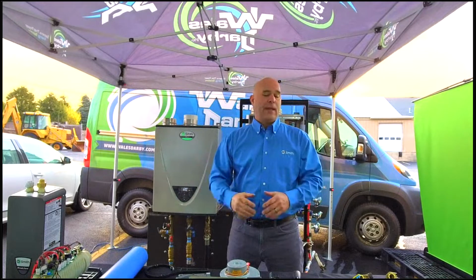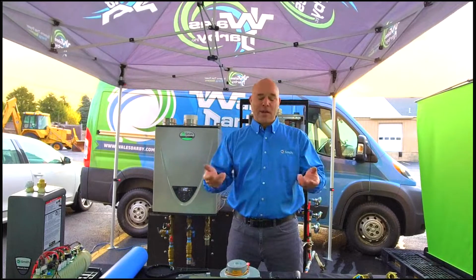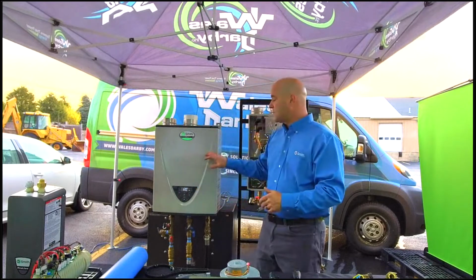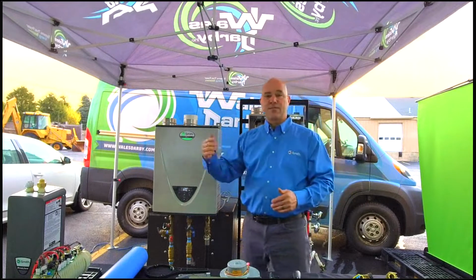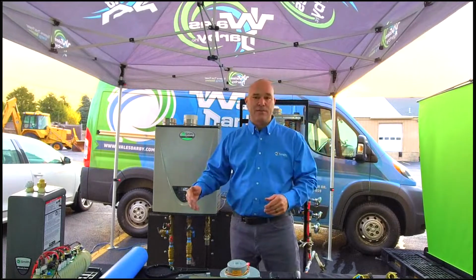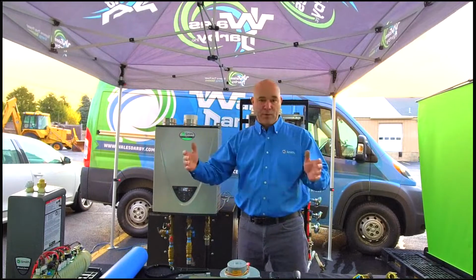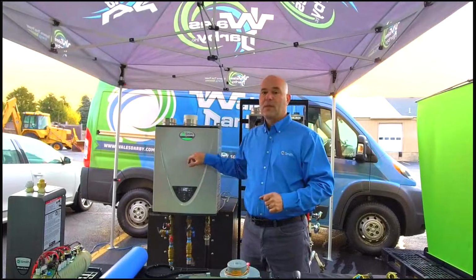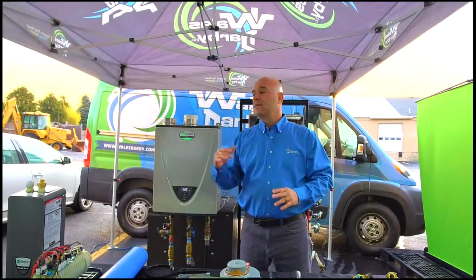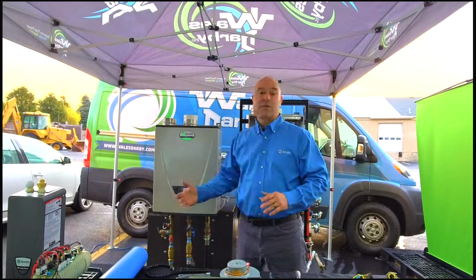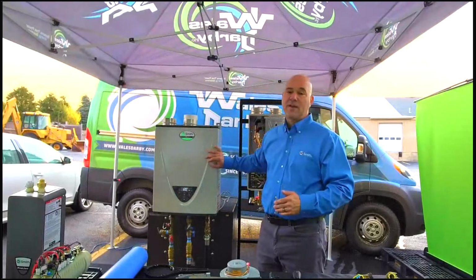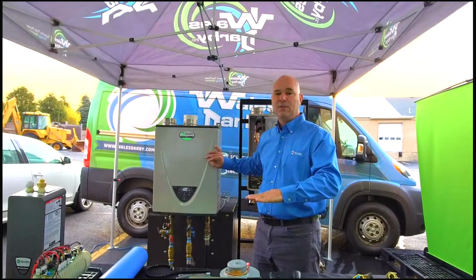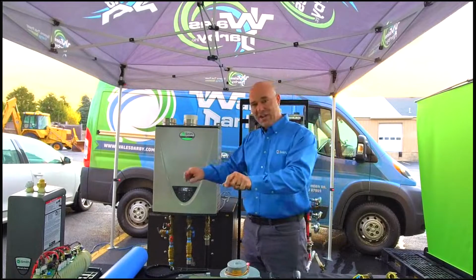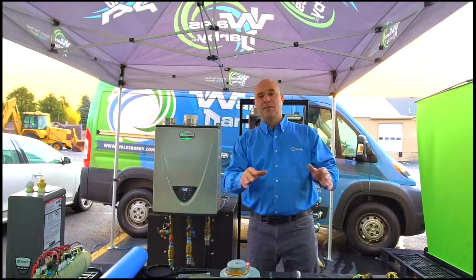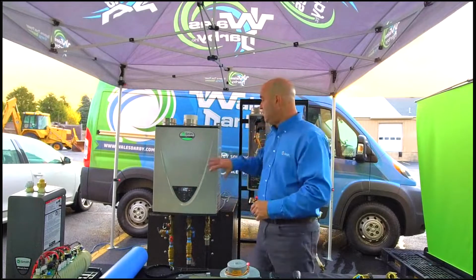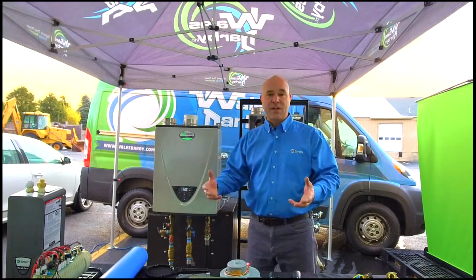So I get up in the morning and get in the shower. As soon as I turn the faucets on, tankless recognizes flow. With this unit, it needs to be a half a gallon of flow. Most units in our industry are right there, 0.4, 0.6, in that range. When that happens, the unit will fire and we will start to produce hot water. The difference is this will fire and then modulate down to the correct BTU to support the load of that one shower. Tank style fires at full capacity all the time, every time, doesn't know any different, doesn't modulate. This will modulate to match the load of the shower at that moment.